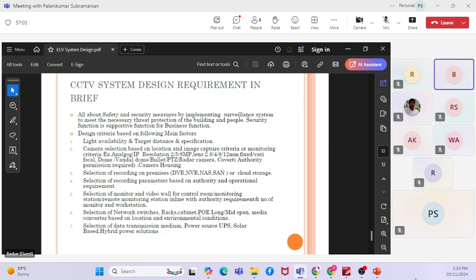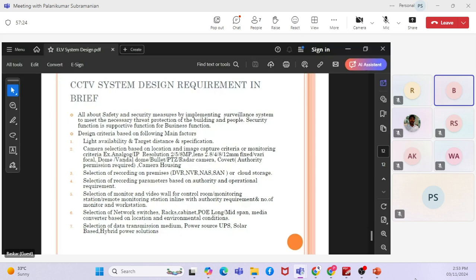Some authorities say it has to be IP based only, which means you definitely have to go with Cat6 cable or Cat5e cable or Cat6e cables. It's a network cable. Otherwise, if it's a small application, small buildings, you can go with a coaxial cable. So it all depends on the camera type; the cable varies. Also, the cable type varies depending on the environmental conditions.